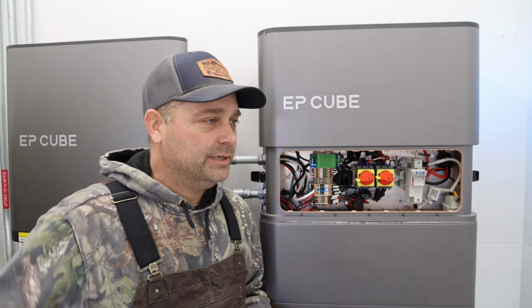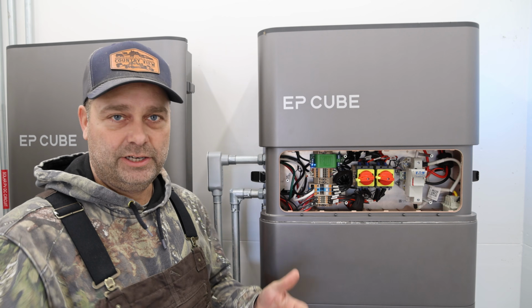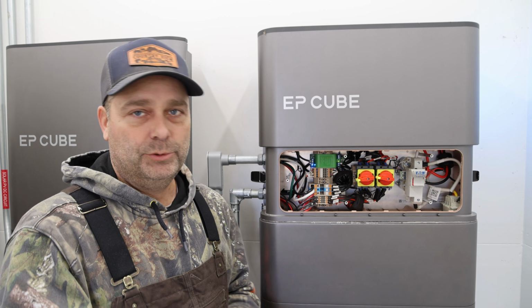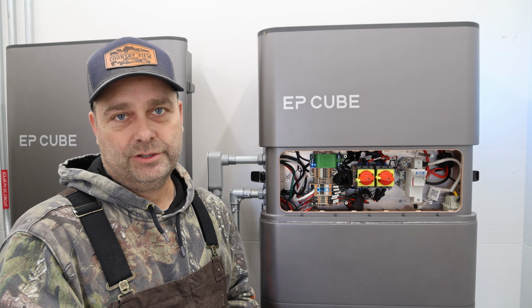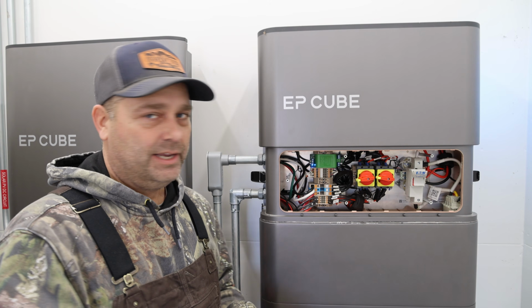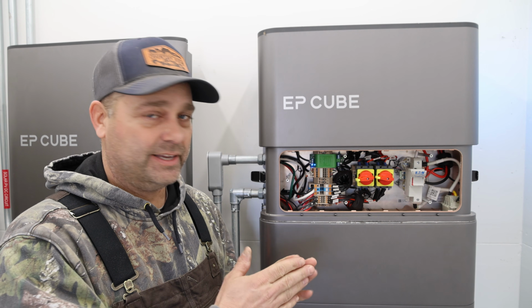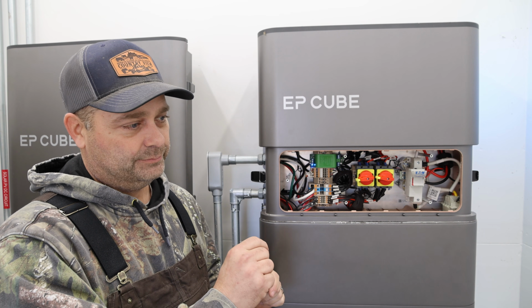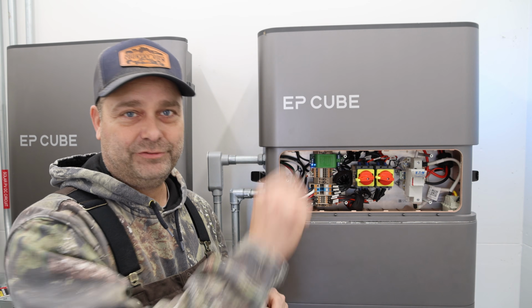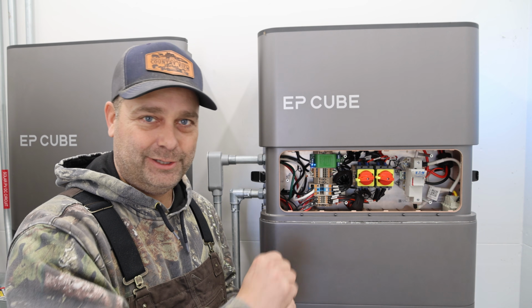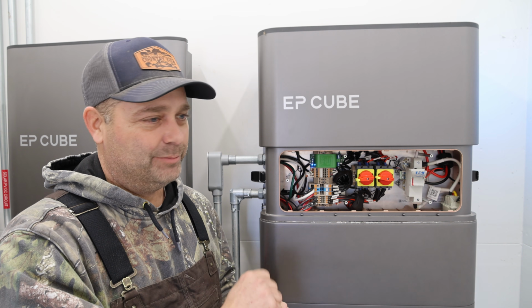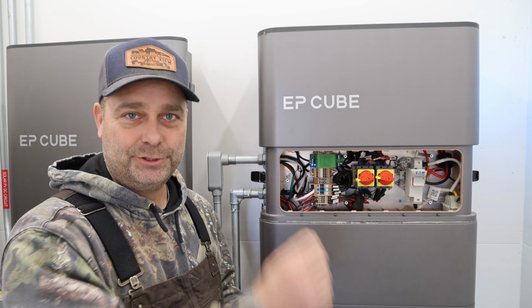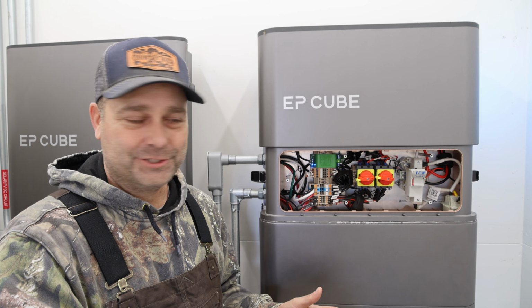So I ended up calling up EP Cube. They've got a number in the app. You can call them, and you can get somebody on the phone within a couple minutes. I explained the whole troubleshooting problem to them, and they could see the data on the screen. They could see that input number 2 would come on for just a second and then error out. Input number 1 would just error out. But when I hooked it up to number 3, they could see that it would work. I also hooked it up to number 4, and it worked just fine.